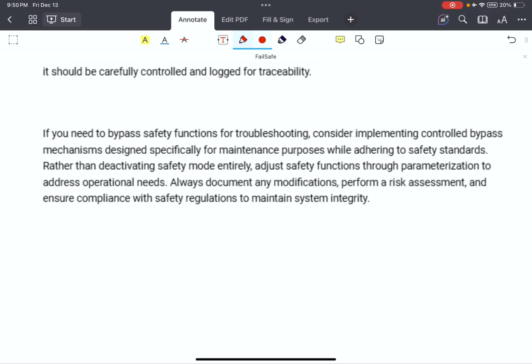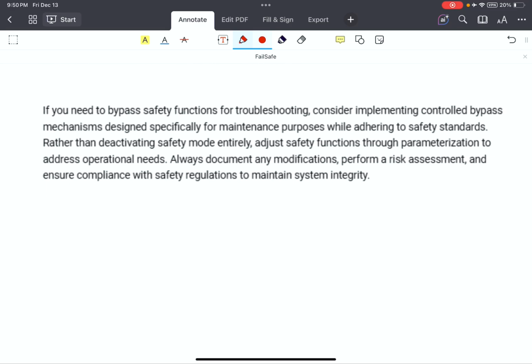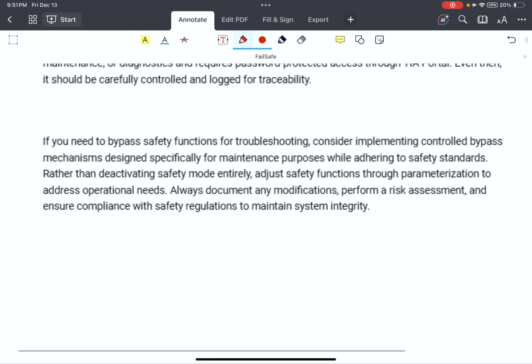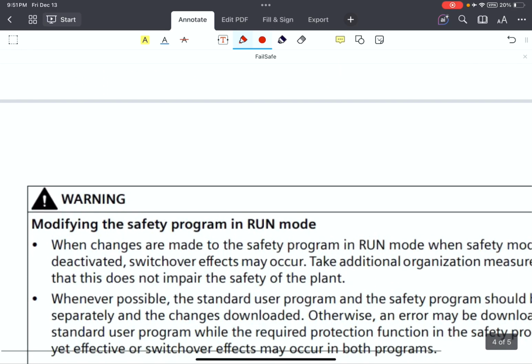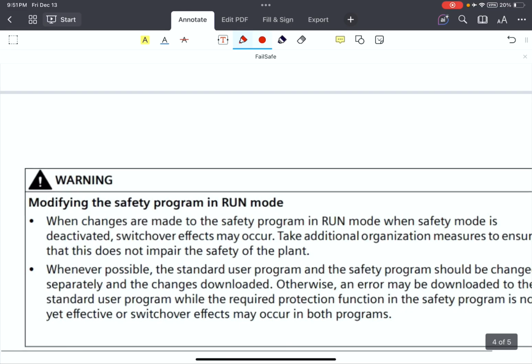If you need to bypass safety functions for troubleshooting, consider implementing a controlled bypass mechanism designed specifically for maintenance purposes while adhering to safety standards. Rather than deactivating safety mode entirely, adjust safety functions through parameterization to address operational needs. Always document any modification, perform a risk assessment, and ensure compliance with safety regulations to maintain system integrity. So it's not a very straightforward or easy task to do.